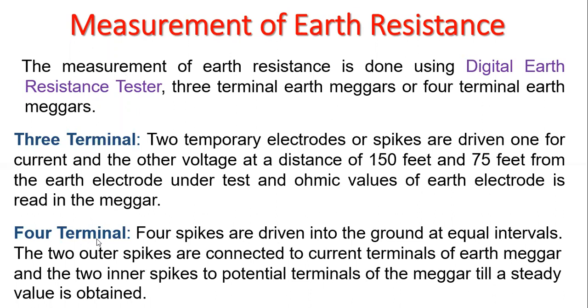Then next, the 4-terminal earth megger. In that, 4 spikes are driven into the ground at equal intervals. Suppose we consider an interval of 15 meters, then all the 4 spikes, or electrodes, are placed at an equal interval. Then the 2 outer spikes are connected to the current terminals of the earth megger and the 2 inner spikes to the potential terminals of the megger, till a steady value is obtained. The steady value of resistance is obtained with the help of this 4-terminal earth megger.